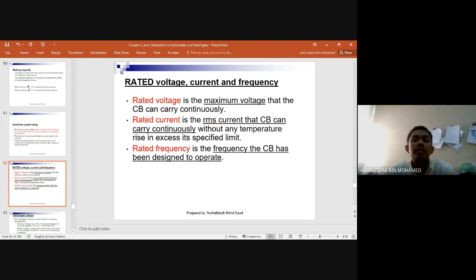Okay, next is the definition of rated voltage, current, and frequency. Rated voltage is the maximum voltage that the CB can carry continuously. Maximum voltage. Rated current is the RMS current that the CB can carry continuously. And rated frequency is the frequency that the CB has been designed to operate at.